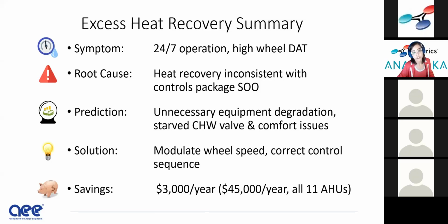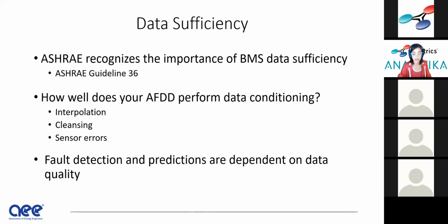And in that way, we can help justify capital projects. We do that a lot, where you can justify installation of a heat recovery coil, or you can justify the installation of additional sensors and BAS points by saying, if you do that, we can save, you know, $30,000 a year, for example, on heat recovery. In this case, it was $3,000 a year for that one air handler, and for all 11 air handlers, it was $45,000 a year. And again, that doesn't take into account the other consequences.